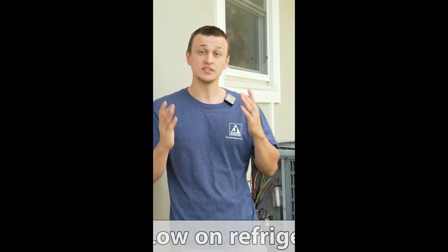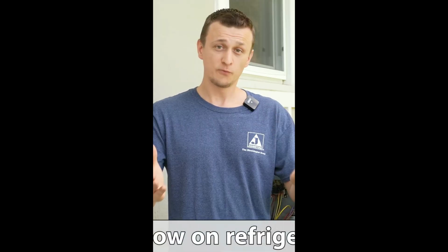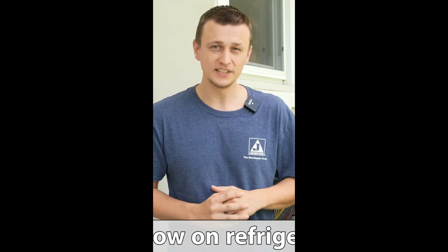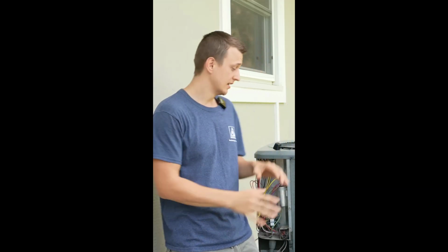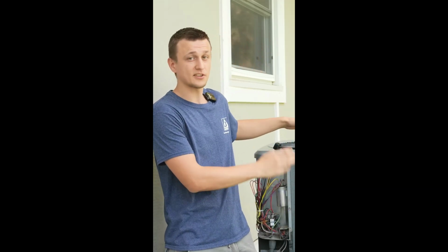And another reason why an air conditioner stops working right is because it is low on refrigerant. Unfortunately, this problem is a little harder to deal with, and most likely you will need a technician to come out to get that fixed. The most common symptom of a unit being low on refrigerant is when everything is running, the fan inside is running, everything outside is running, the fan and the compressor, yet the house is not cooling off.